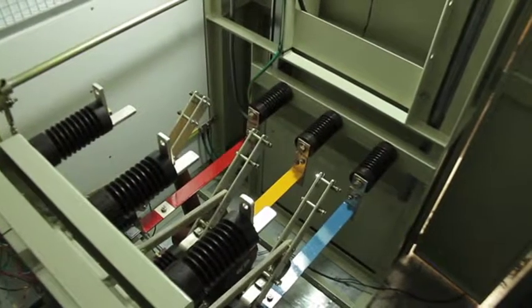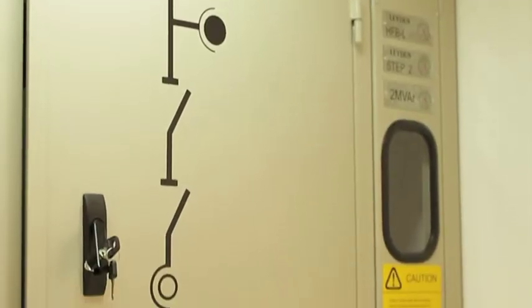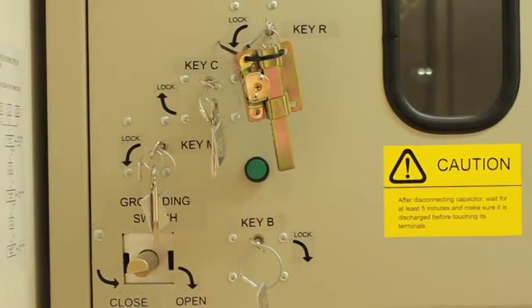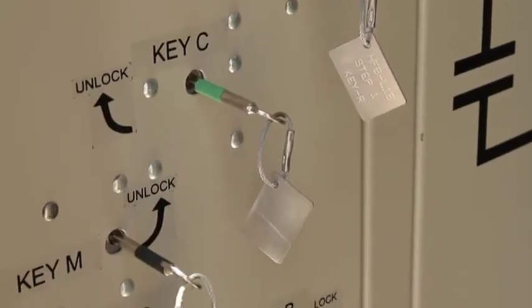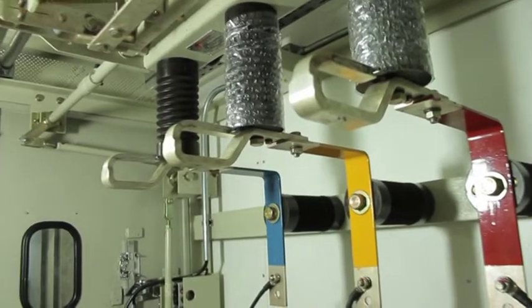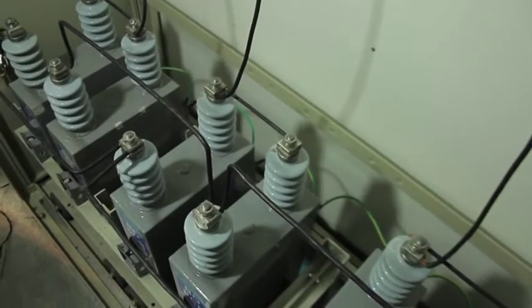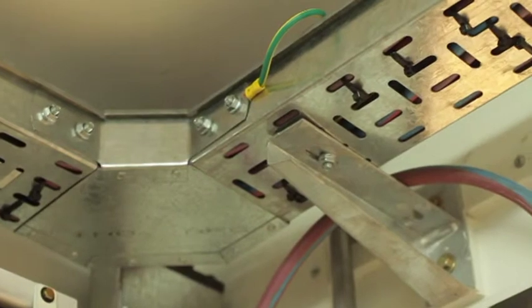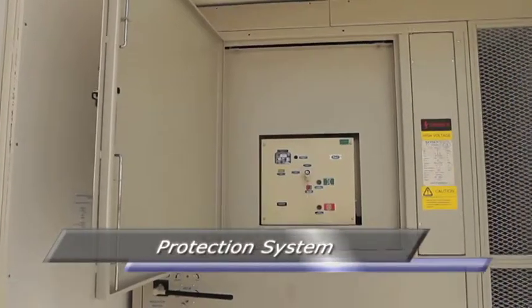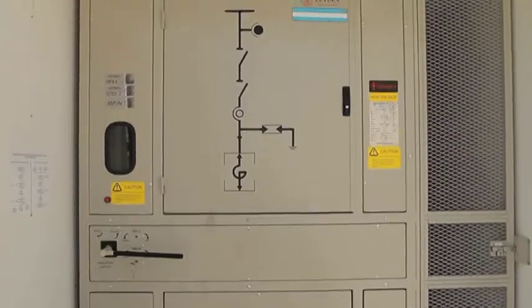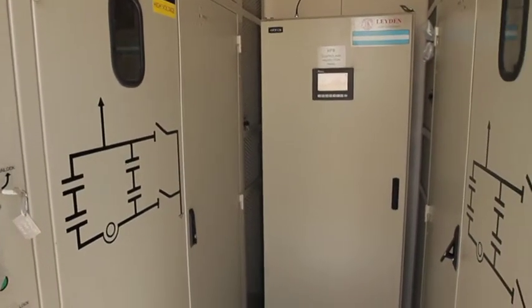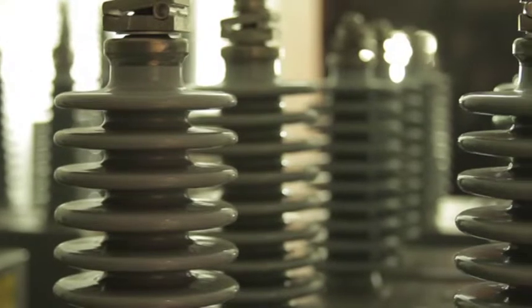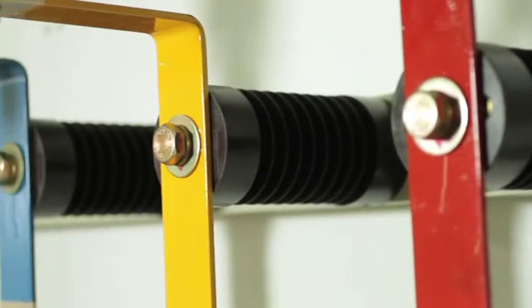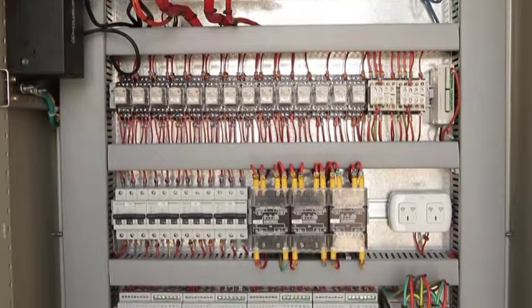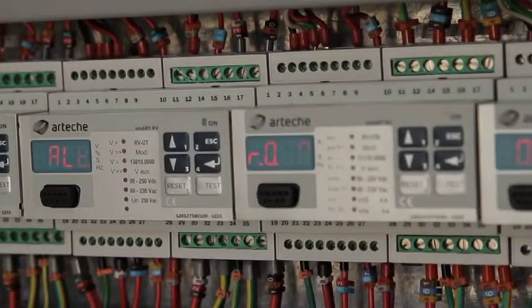The filters are fitted with a mechanical interlocking system which assures that the disconnection and opening of equipment for inspection and maintenance are carried out under proper safety conditions for operators. Harmonic filter banks are protected against neutral unbalance, over and under voltage, overload, short circuit, and very high temperature in the mobile electrical room. Analog signals from primary elements, PTs, CTs, and thermocouples are digitized and fed into the control and protection PLC located in the local control panel.